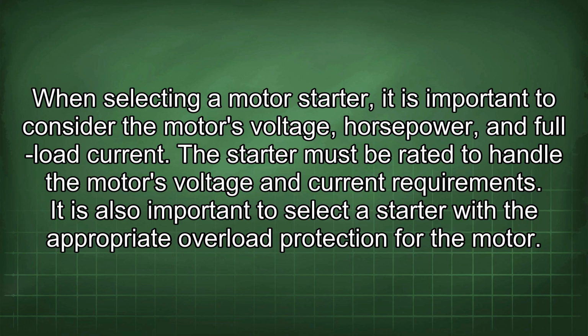When selecting a motor starter, it is important to consider the motor's voltage, horsepower, and full load current. The starter must be rated to handle the motor's voltage and current requirements. It is also important to select a starter with the appropriate overload protection for the motor.